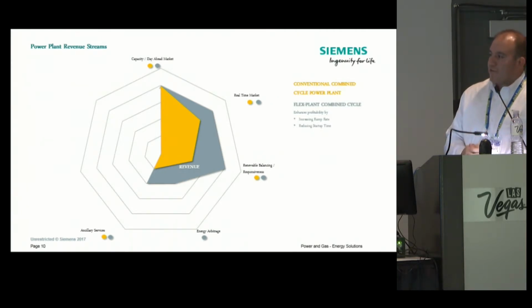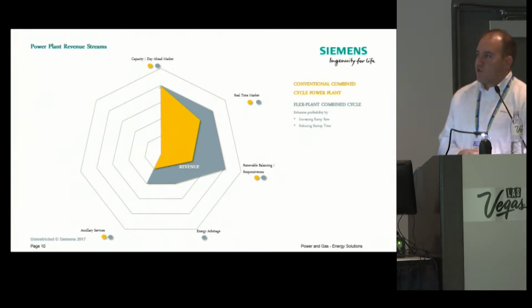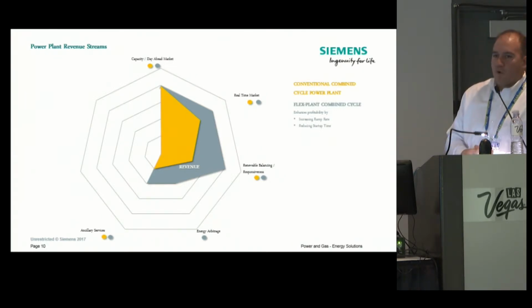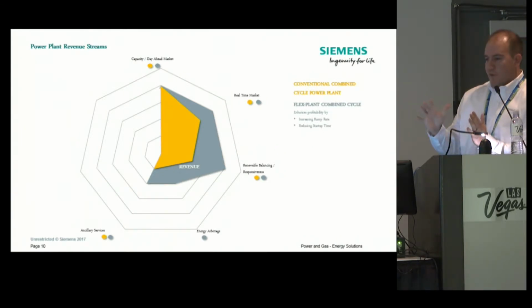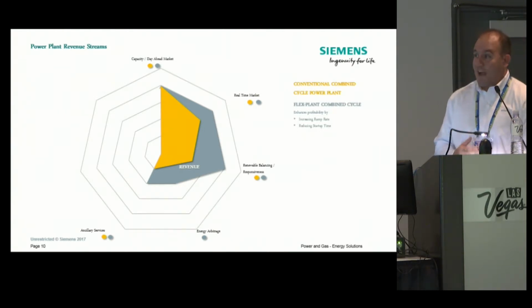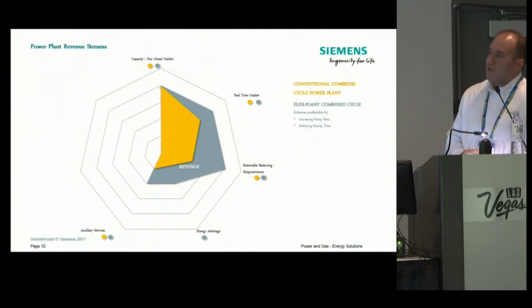The bottom right there is energy arbitrage, which in its simplest form means you buy power, or on the battery example, you get paid to make power and then get paid to sell it too. In this example, if power is on peak and you're making a lot, then all of a sudden you spike down—say you're in ERCOT and prices fall out of the bottom—how fast you can ramp down or get offline, or the minimum load you can turn down to, is just as important as how fast you can ramp back up, or the max load you can get to.